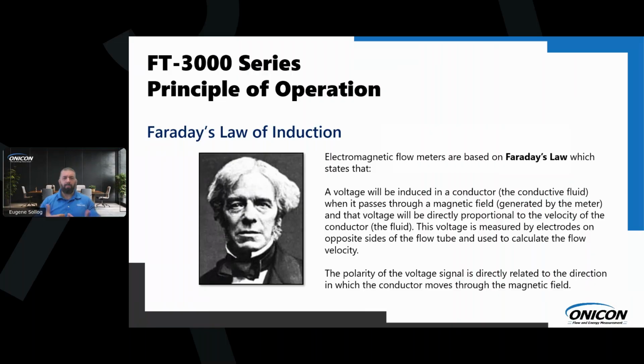So, the principle of operation: the mag meter uses Faraday's law of induction. Basically, a voltage is induced in a conductor. In this example, the conductor is water, the fluid in an HVAC system, when it passes through a magnetic field, which we are creating with our flow meter. That voltage is directly proportional to the velocity of that conductor, the water in the pipe.